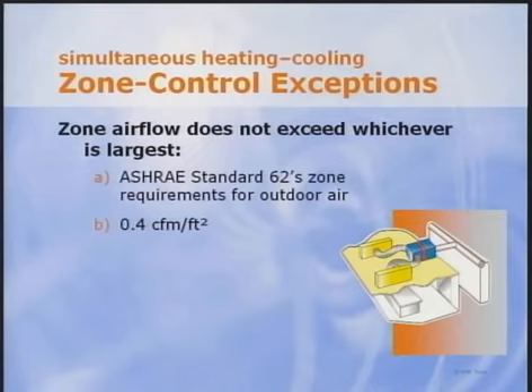Today's energy regulations require better glass, more insulation, and lower lighting power densities than in the past. The bottom line is a reduction in space sensible cooling load requirements. Since the space airflow required is dependent on this sensible load, if the same supply air temperature is used, the design space airflow is lower than it was in the past. So using 0.4 CFM per square foot as the reheat minimum set point may allow a higher airflow to be reheated using new energy than the next limit.